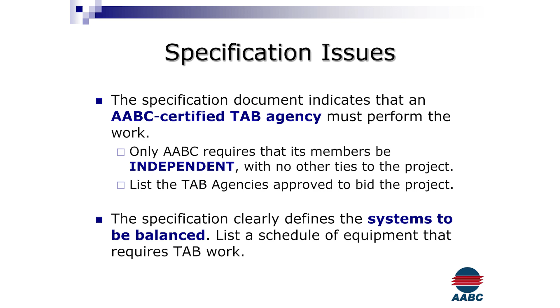When it comes to specifications, the documents need to indicate that there's some independence there. An AABC certified TAB agency performing the work should have no ties to any other mechanicals—they're not selling filters, they're not installing ductwork or pumps. There's an inherent bias for companies that are installing equipment and also performing the balance, and now even performing some commissioning, as some firms are starting to do.